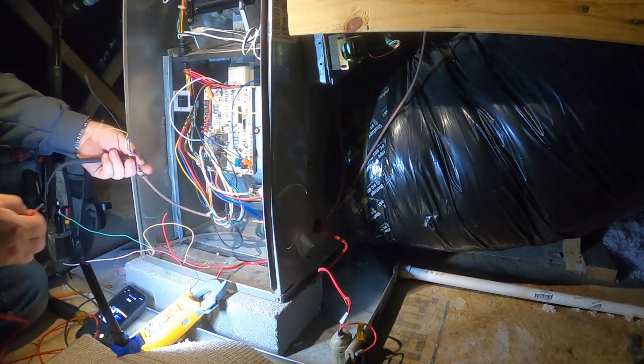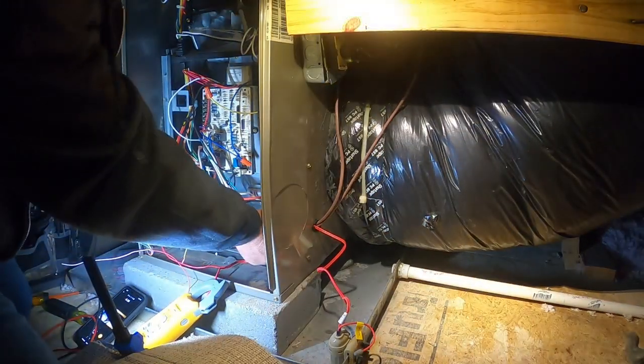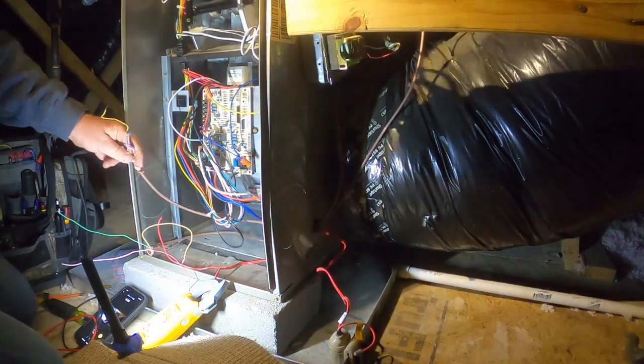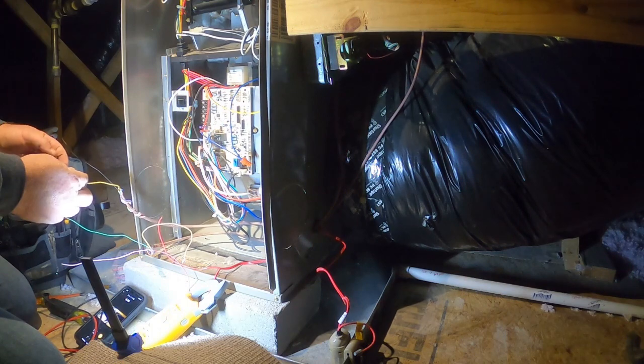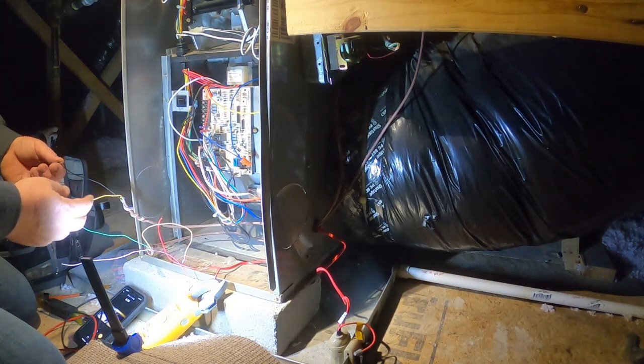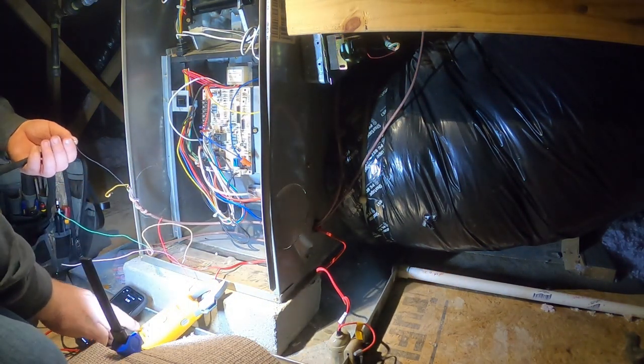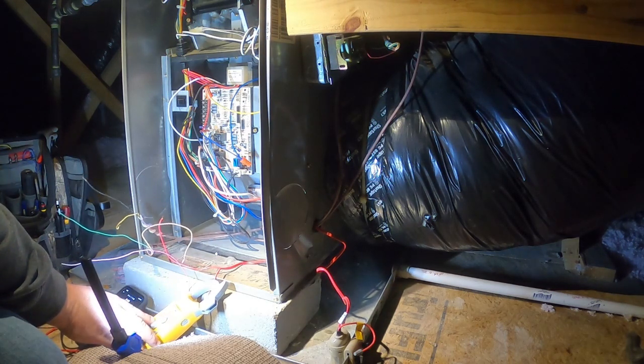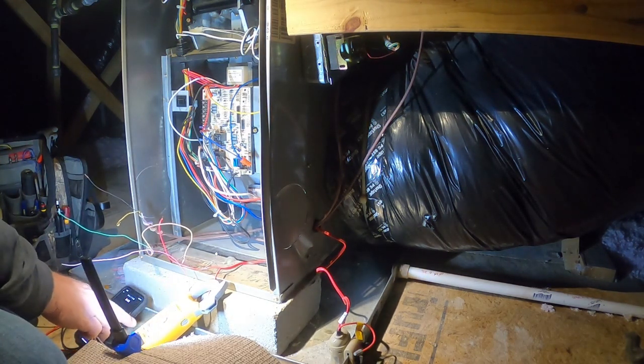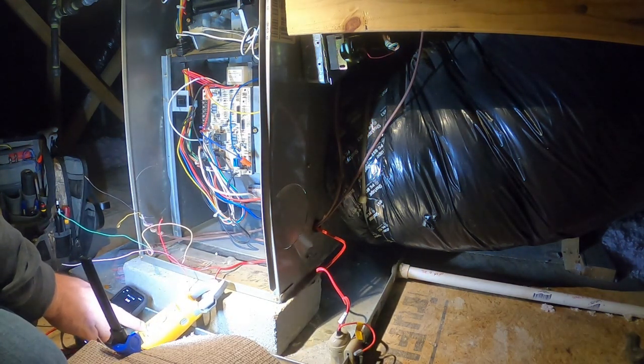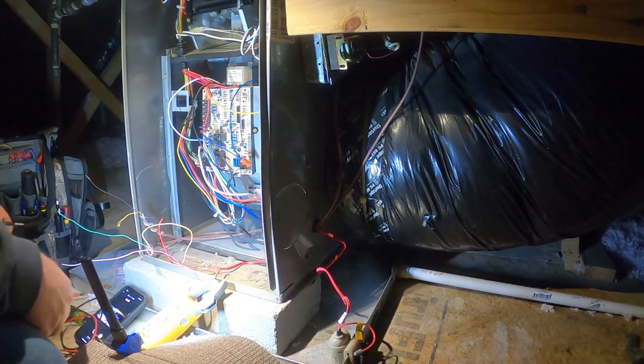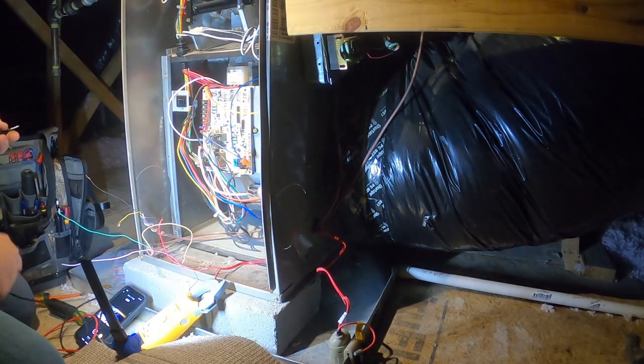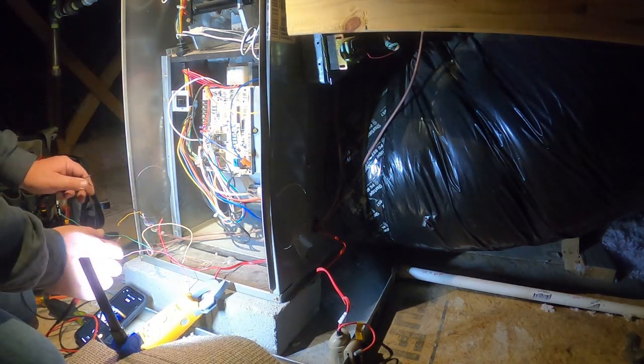That is our wire going to the outdoor unit. Let's go back real quick, I had it set for continuity, let me just set it for the regular ohm range, by itself, because it will show continuity through the coil on the contactor.